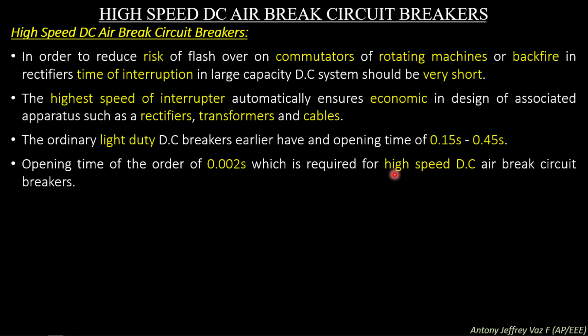circuit breakers. So when the voltage rating of the DC system is very high, the interrupting time must be very small, in the order of 0.002 seconds. The interrupter should interrupt the arc within 0.002 seconds, which is much less than the earlier light duty circuit breaker's 0.15 to 0.45 seconds. So these high speed DC circuit breakers should have a very short operating time.